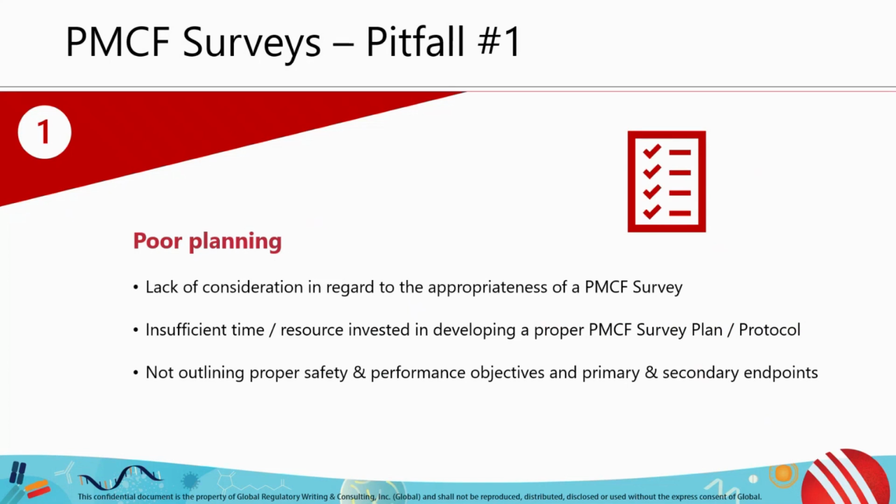So starting with planning, when there is a lack of consideration in regard to appropriateness of a PMCF survey, there's bad news at the start. Don't just rush into a survey because it is the cheapest method or the quickest method. You should do a survey if it's the right method. So really think about that justification. And if you are going to do a survey, like I said, invest in the time and the resource to develop a proper survey plan and protocol. If you get that planning right, your survey will be designed properly and the data you get will be able to be used and accepted by the notified bodies. With that planning, make sure you outline the proper safety and performance objectives and endpoints. We very regularly see manufacturers come to us and say, these are the questions we want, but they're not in line with any safety and performance objective.